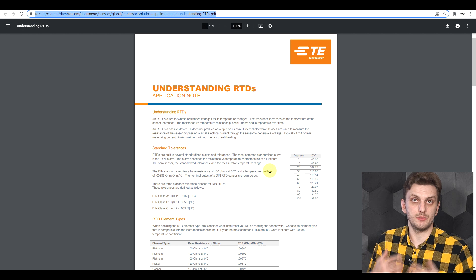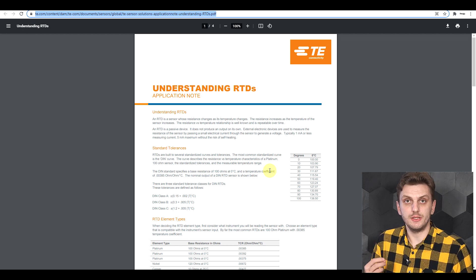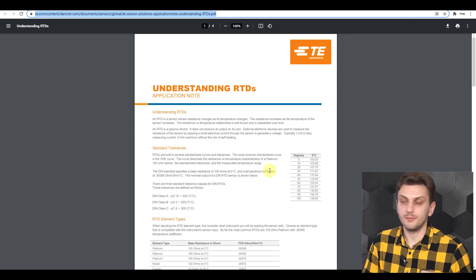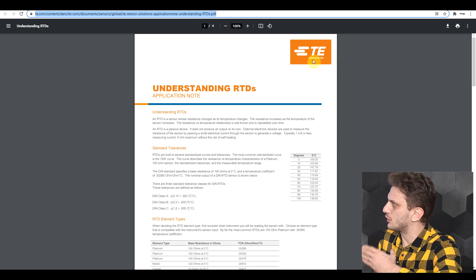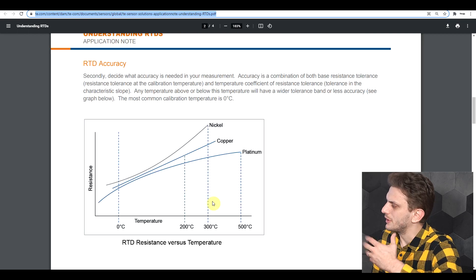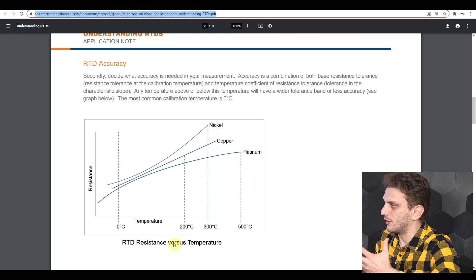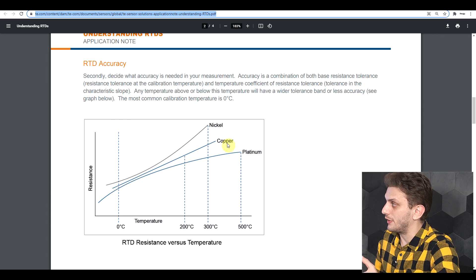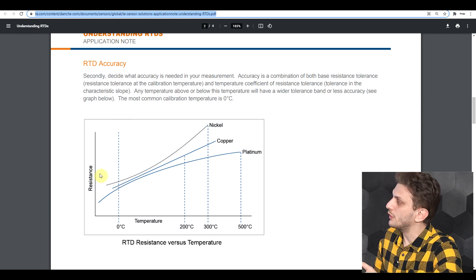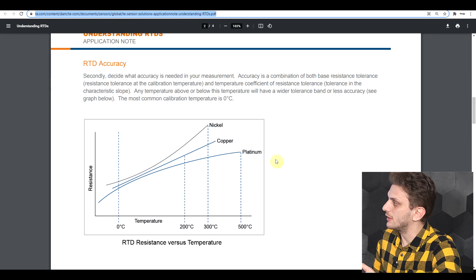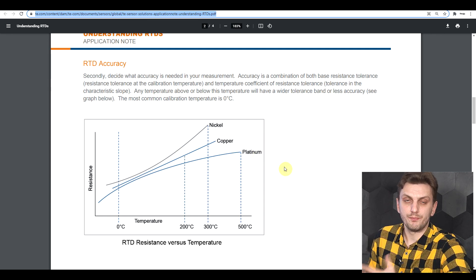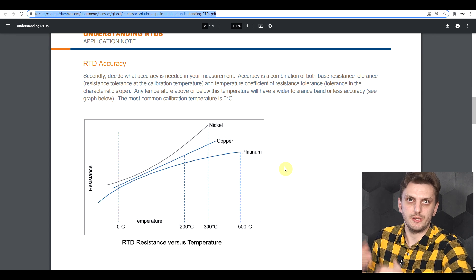Regardless of the complexity of the measurement circuit, the RTD is a far more linear device compared to an NTC. If we have a look in this application note from TE Connectivity, we can see that based on the material from which the RTD is made, you can have either a fairly straight variation like with copper, or you can have a slight curvature with nickel or platinum. So you don't have a perfectly linear variation, but regardless it's far more linear than the NTC.